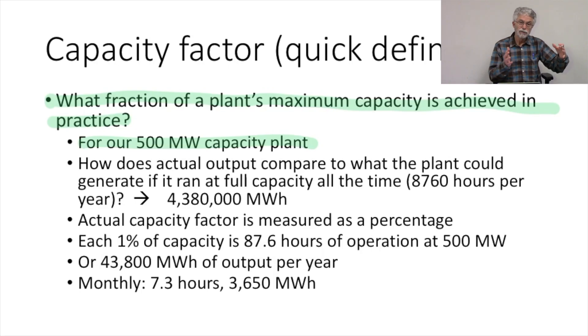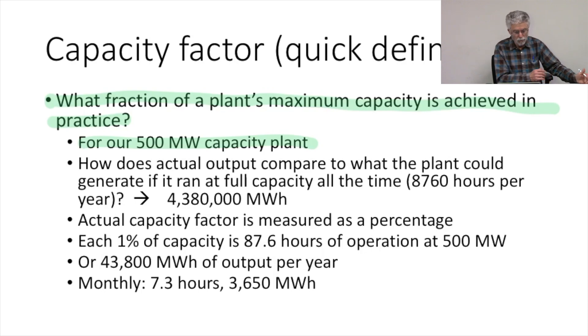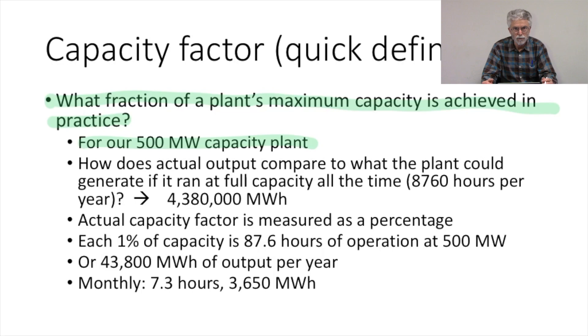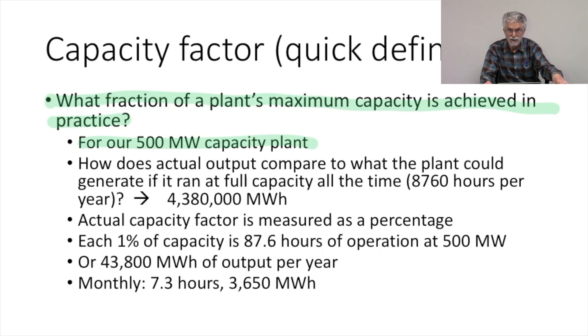The actual capacity factor is measured as a percentage of that total full capacity. We think about what the power plant actually produced and calculate the percentage of full capacity that represents. For example, if this plant were running with a 1% capacity factor instead of 100%, it would be running only 87.6 hours instead of 8,760 hours. Running at 500 megawatts for about 88 hours gives about 43,800 megawatt hours of output per year at 1% capacity.